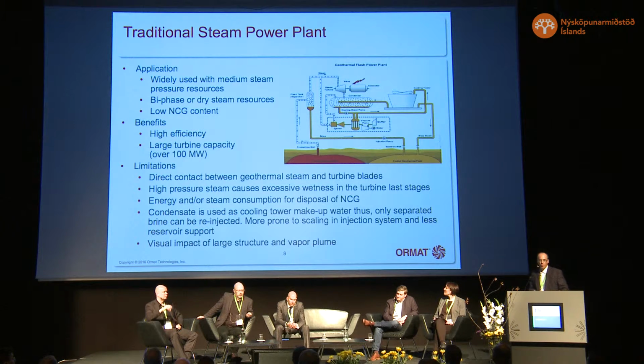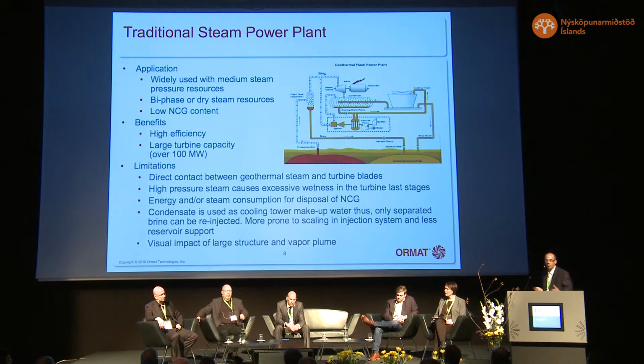The drawbacks of the steam technology are the direct contact between the steam and the turbine blades. The high pressure of steam causes excessive wetness in the turbine last stages. What we are familiar with today is that wetness should not be above 15% at the last stage. Energy and power are used to suck out the NCG from full vacuum to the atmosphere, and the condensate, which is used as makeup for the cooling tower, is not reinjected back to the earth. Thus there is less resource going back into the ground, and it is more prone to scale because all the solids remain with the brine injection and can cause the injection well to be blocked.